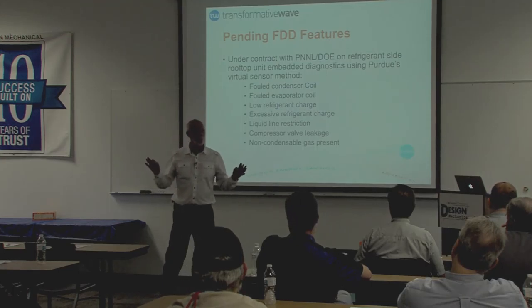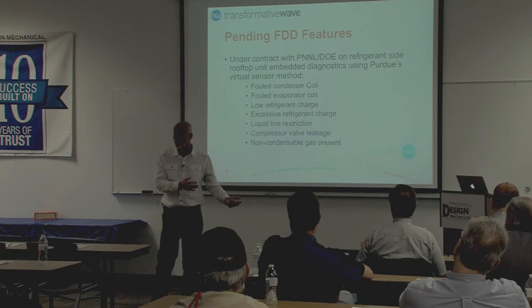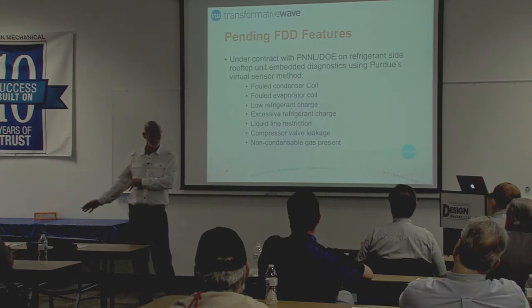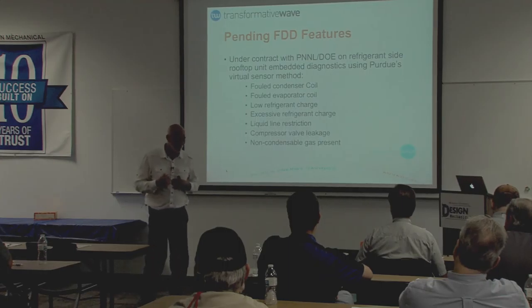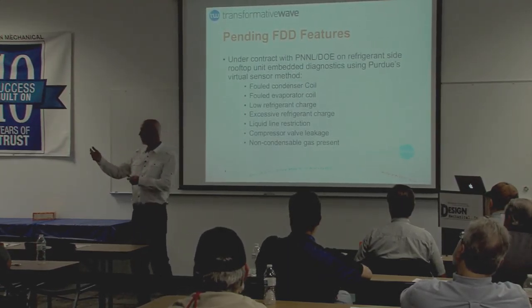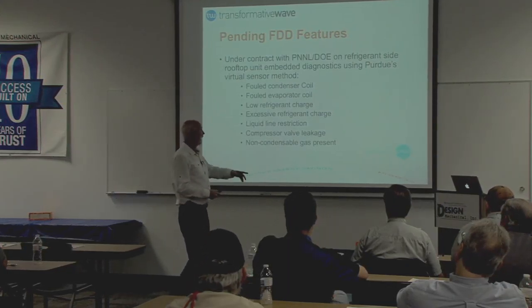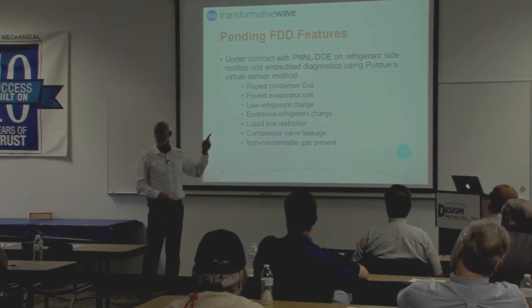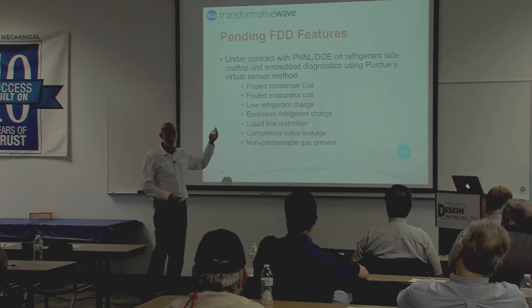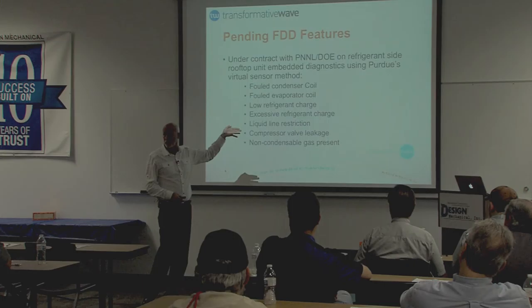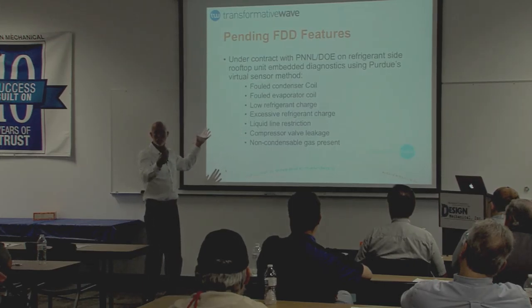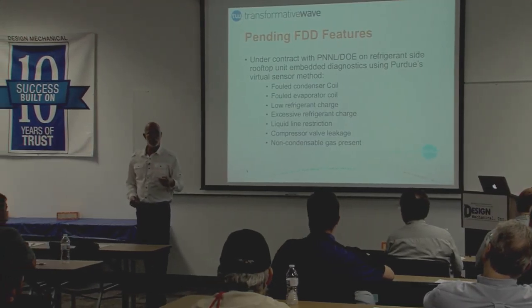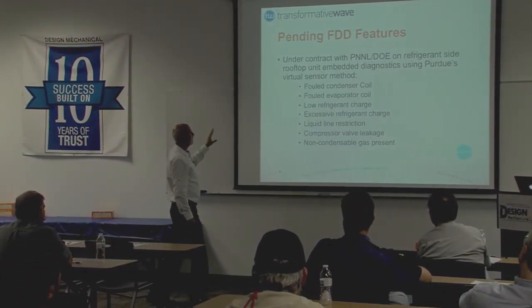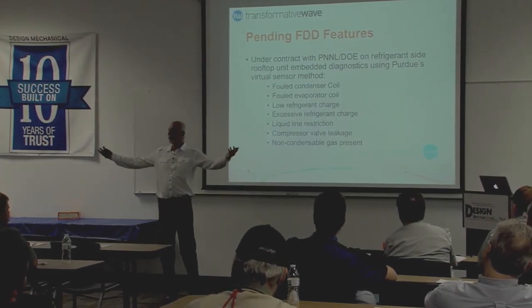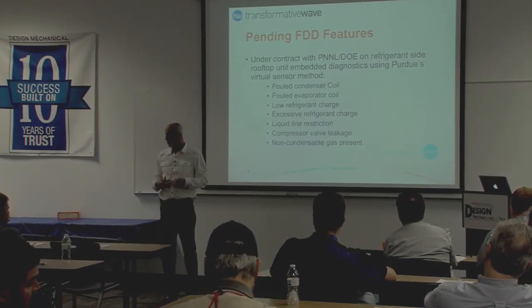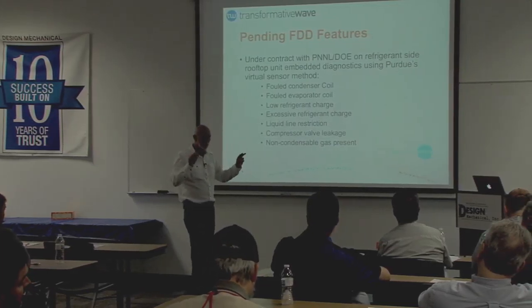Fault detection happens two ways: manufacturers put fault detection into their equipment when they make it, or it's field deployed. We're on that field deployed side. Trane, Carrier, or Lennox - York has a brand new unit coming out with some of this capability built in. A lot of it gets articulated at the unit level up in the machine, but it has BACnet capability. So if you have BACnet through your building control system, like Design Mechanical deploys, they'll be able to articulate these faults for you through their automation system, and we do the same through our more canned approach.